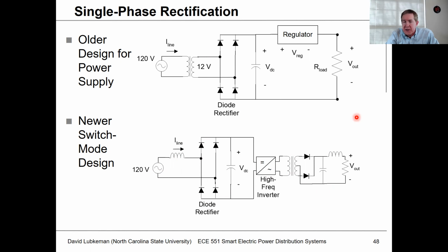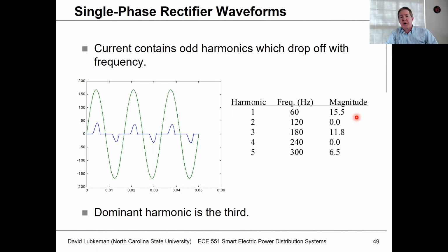What you'll see on these single phase rectifiers is they don't really draw a lot of current, because usually the loads aren't that high. But you would see a current draw in the first half of the cycle and a current draw in the second half in the opposite direction. Usually in steady state, this is normally symmetric. And this would give you odd harmonics like third, fifth, seventh, etc.